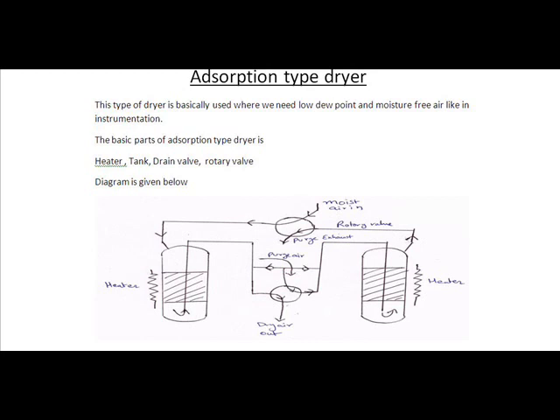As we use the heater here, we see that two columns are used. At any time, one column is drying the air while the other is being regenerated by heating and the passage of a low purge air stream. As shown, column A dries the air and column B is being regenerated. The rotary valves are operated automatically at regular intervals by a timer.